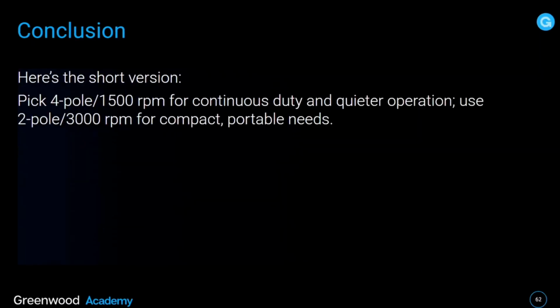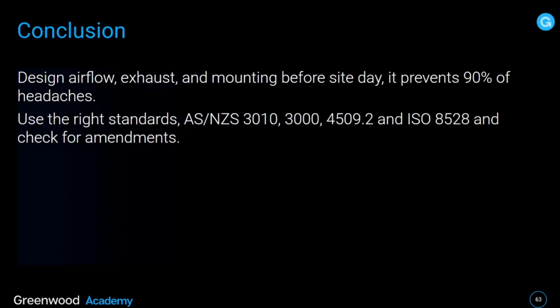Conclusion. Now, here's a short version. Pick 4-pole, 1500 RPM water-cooled for those more sustained loads. Anything else, you can go maybe 3000 RPM water-cooled or air-cooled. Design airflow, exhaust and mounting before site day. It prevents 90% of headaches. Use the right standards and check for amendments. It's really important to check for amendments with the standards.